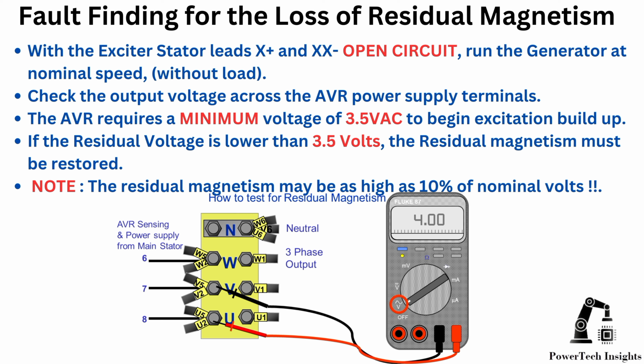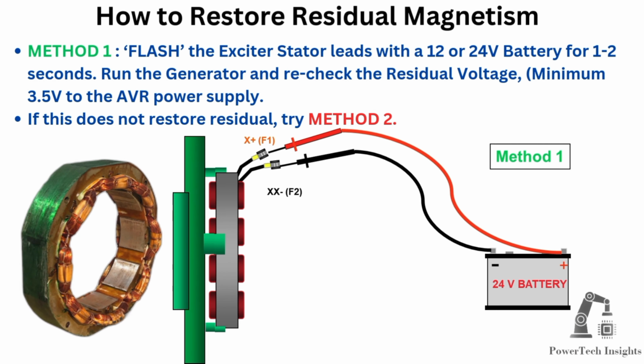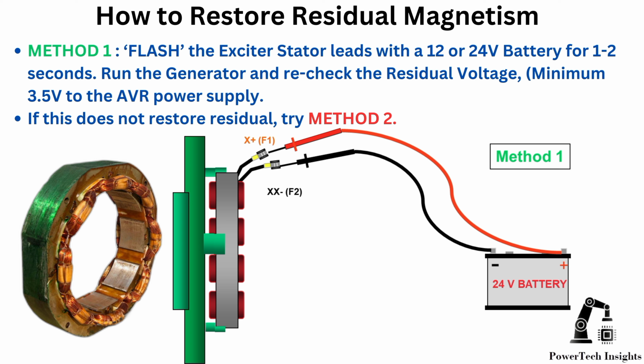Note, the residual magnetism may be as high as 10% of nominal volts. How to restore residual magnetism? There are 3 methods to restore the loss of residual magnetism. Let's discuss them in detail.